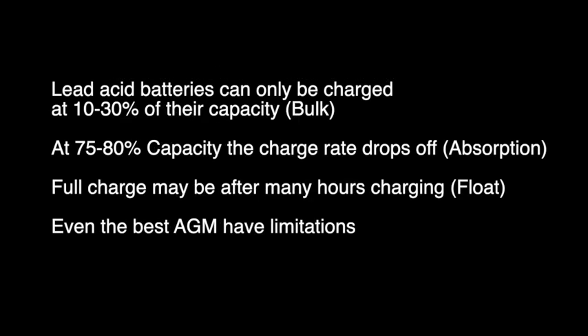There's also another issue around conventional lead acid batteries. They can only be charged at 10 to 30% of their capacity, that's bulk. At 75 or 80% capacity, the charge rate has to drop off and they go into absorption. Full charge may take hours of charging on float. Even the best AGM batteries still have their limitations. So you see, it's not just about your solar, it's about your batteries too.